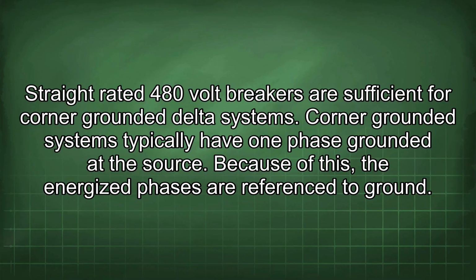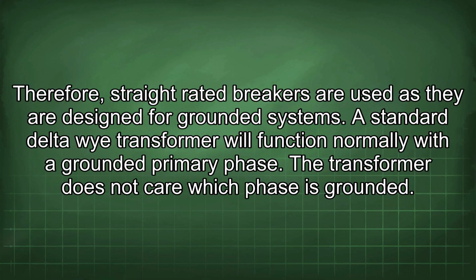Straight-rated 480-volt breakers are sufficient for corner-grounded delta systems. Corner-grounded systems typically have one phase grounded at the source. Because of this, the energized phases are referenced to ground. Therefore, straight-rated breakers are used as they are designed for grounded systems.